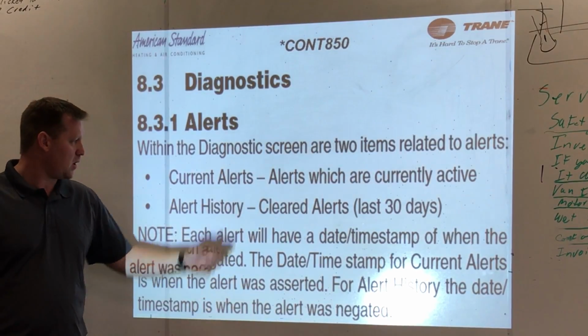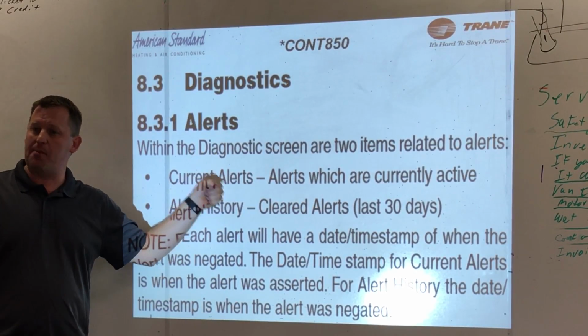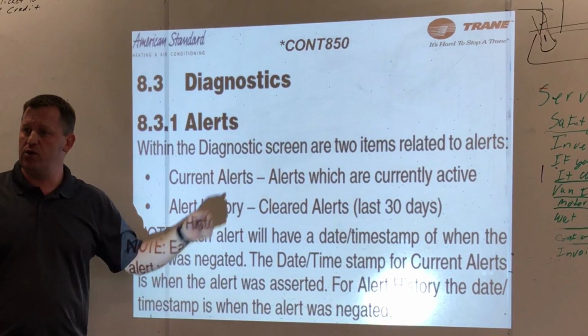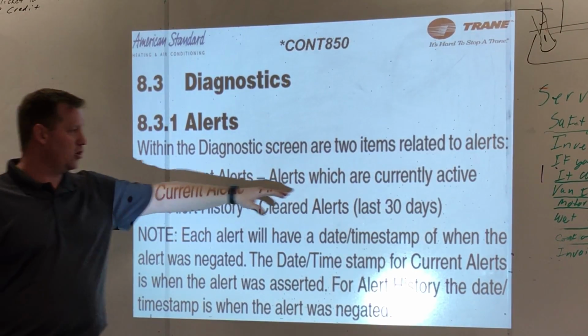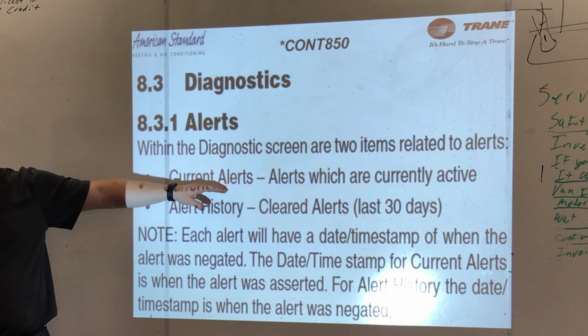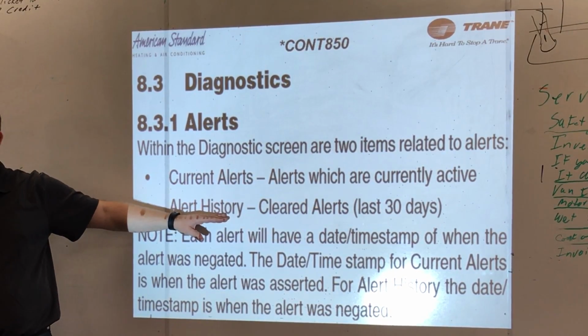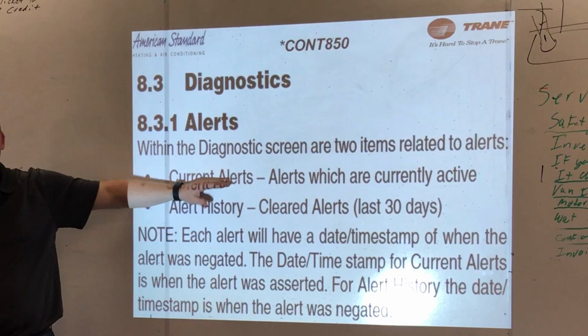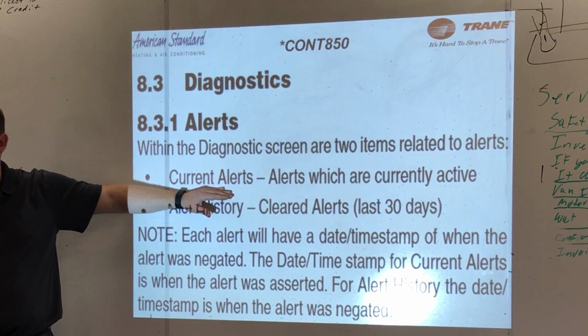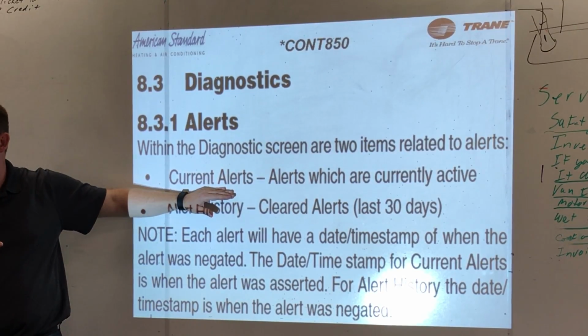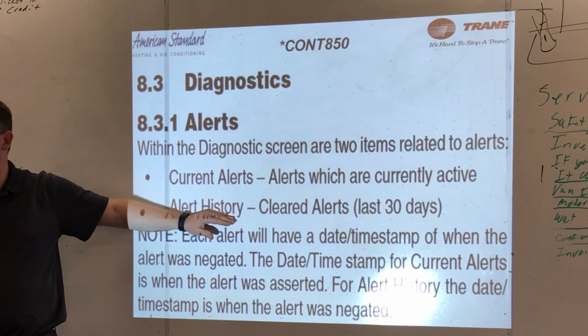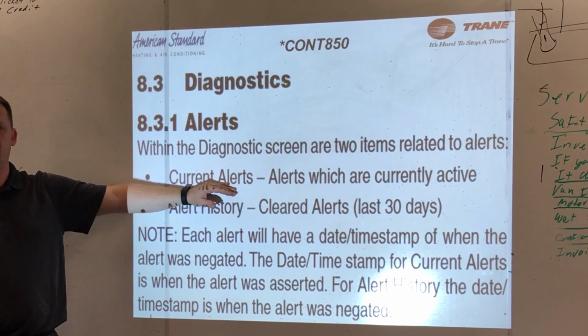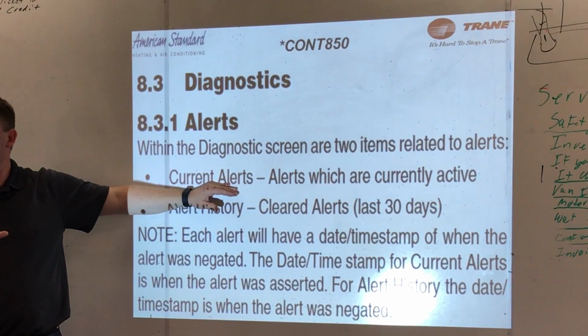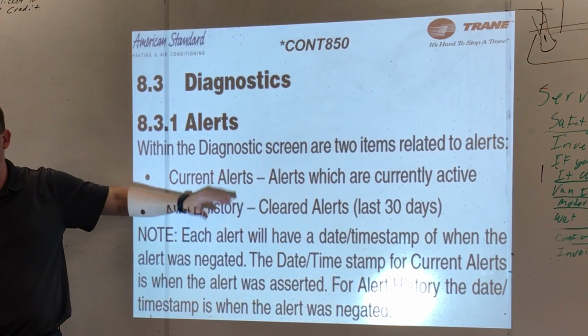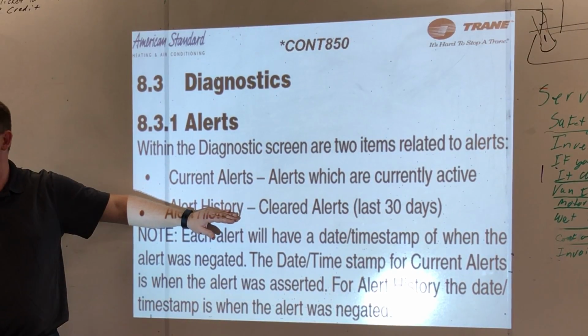So, with communicating equipment, we get a lot more alerts, right? Because now we know when things are happening. Current alerts are alerts that are currently happening. Alert history is alerts that have happened within the last 30 days. So I get a lot of questions. Hey, I've got a current alert right now, how do I get rid of it? Fix the problem. Once you fix the problem, then it goes into alert history. So if it's an outdoor temp sensor error, fix whatever's causing it, the problem goes away and goes into the alert history. Okay?